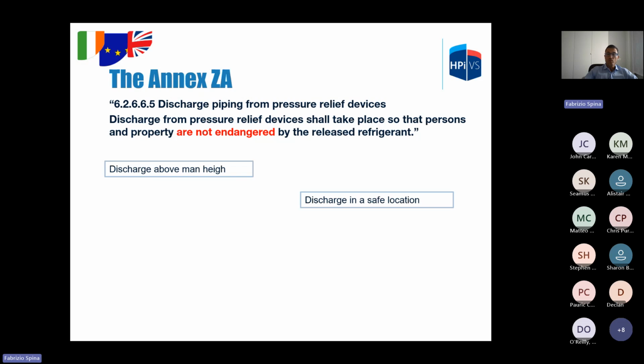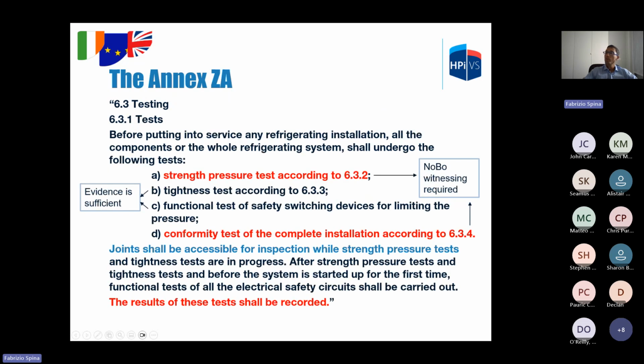Discharge from the pressure relief valve must be in a way that persons and property are not endangered. That means, for example, discharge above man height or in a safe location. Testing.